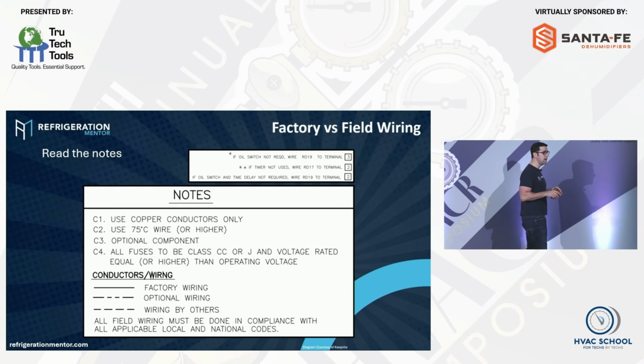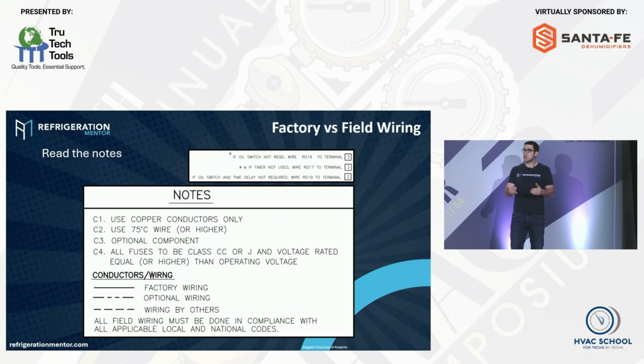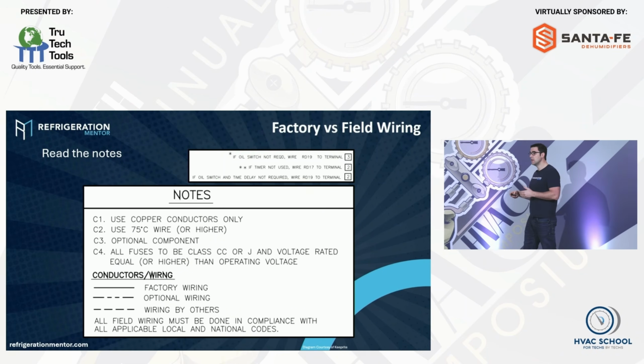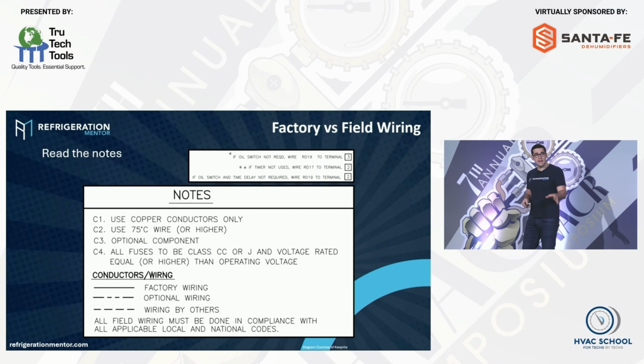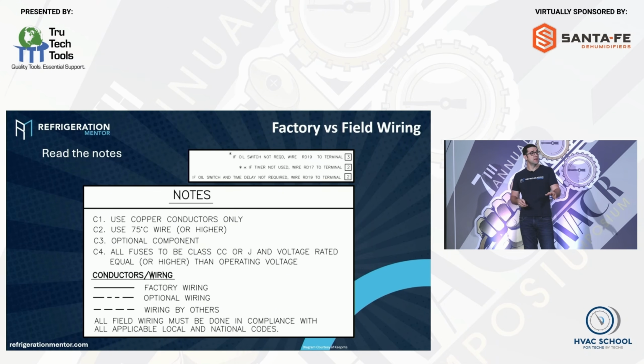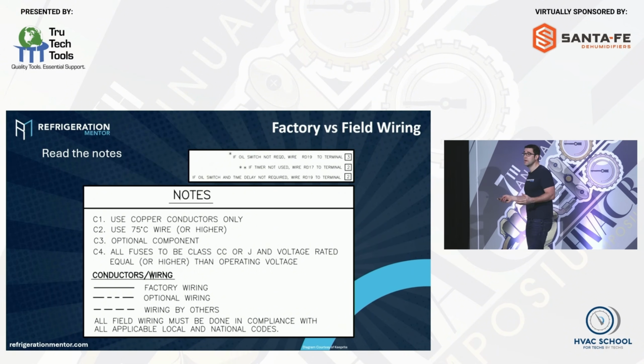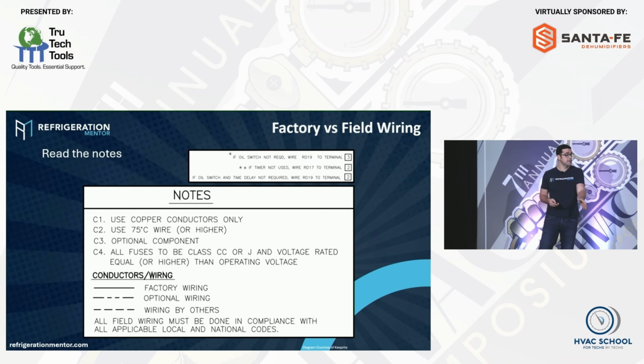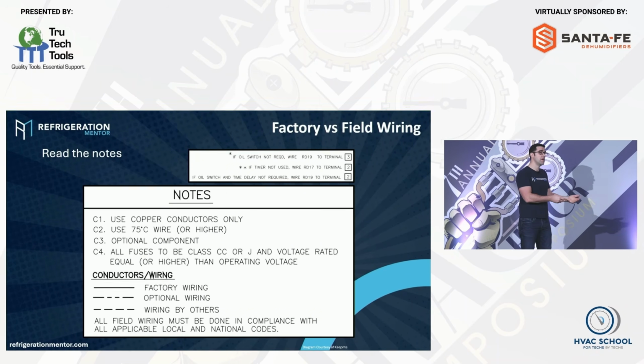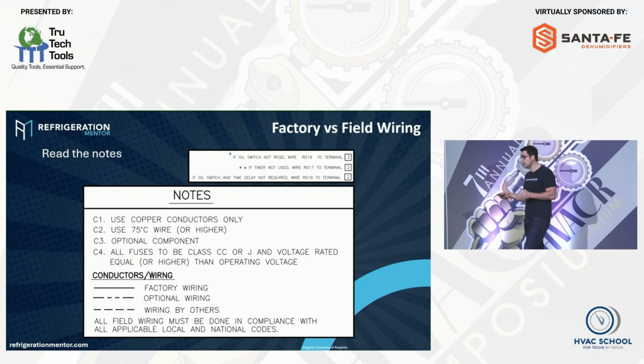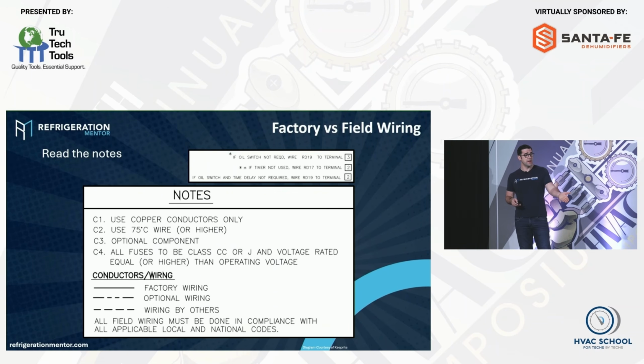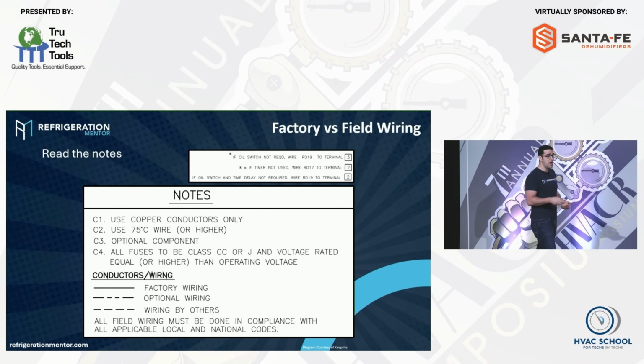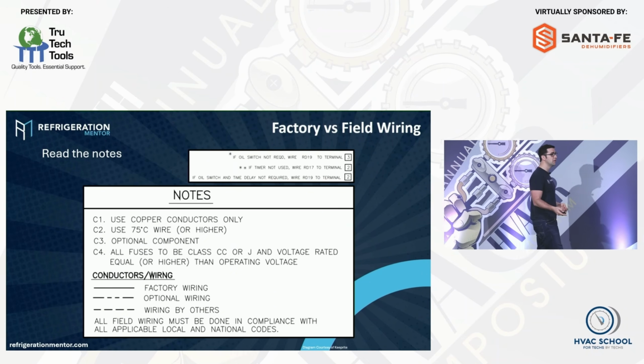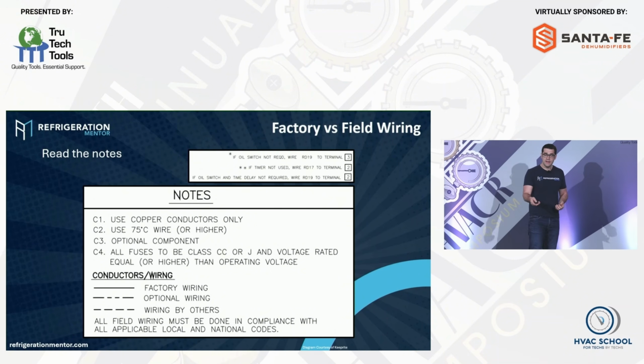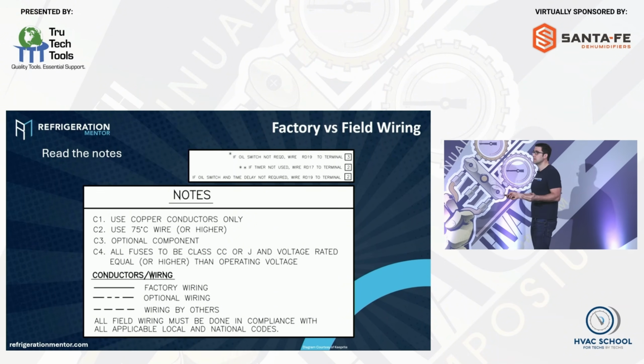I've seen this multiple times in training programs. I go to startups a lot of the time. And I've seen many times people send me pictures and say, hey, Trevor, system's not working. And then some of the main sensors that need to be wired up are not even wired up because the contractor or the technician didn't take a look at the different lines that need to be wired up or not wired up. Condensing unit manufacturers are great for finding this out. Right here, the straight line wire comes from the factory. Optional wiring if you have something like a low ambient control or a specific control on that. And then field wiring by others. That is us. We need to set that up.